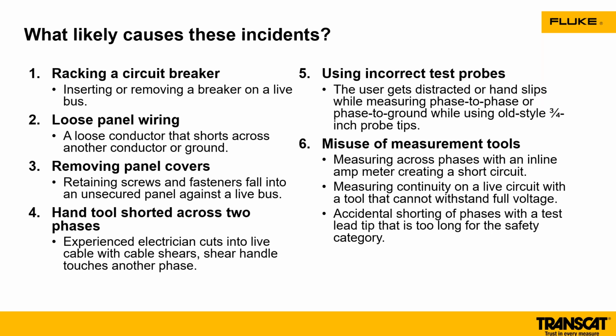Now, using incorrect test probes. Test probes are designed to be able, depending on your category environment and how much exposed metal is on the end of your test probe, as you saw in that previous picture, that arc blast or that arc fault was happening between those two exposed metals of that probe. So making sure you use the right probes for your category environment. And then maybe the measurement tool that you're using causes that arc blast and that arc fault in between it. Something in the meter created that short circuit. Maybe you were in the continuity mode when you were trying to make a voltage measurement. All of that plays into some of these incidences that could be caused that.